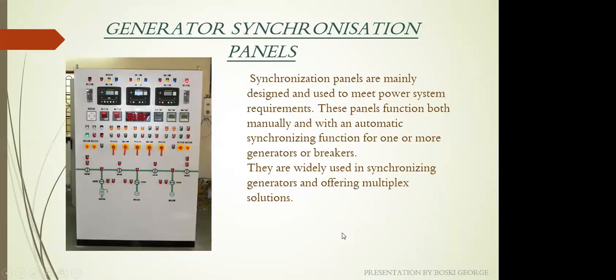These are generator synchronization panels. If you want to run two or three generators, alternators, in parallel, we have a panel called DG synchronization panel. This panel synchronizes these DGs so they run in parallel and share the load required in the system.